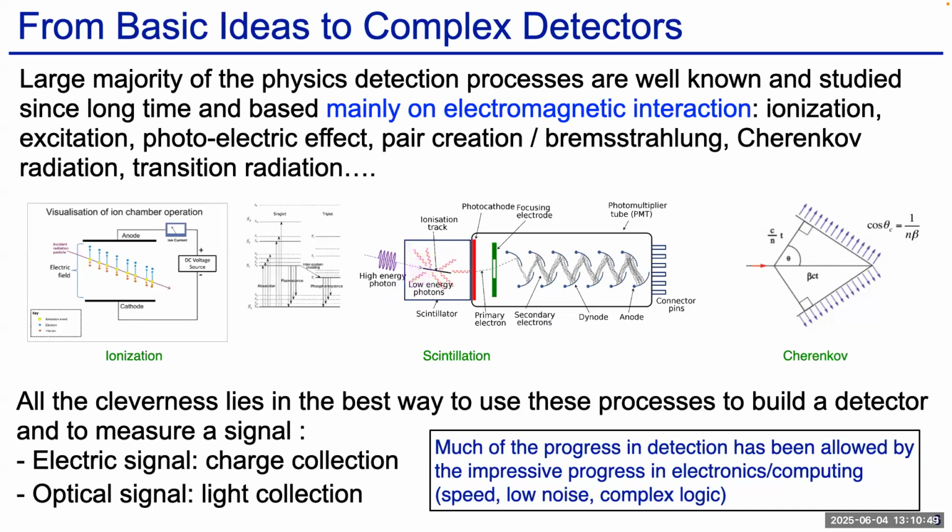Now, how do we detect photons? In the good old days, we did that with photomultipliers that have here a photocathode, then a focusing electrode, and then you have here these dynodes. They hit the first one, they create electrons. They hit the second one, and they create more and more electrons until you have a very strong signal which you read out. Those are hardly used anymore. We have silicon photomultipliers and other things, but the principle is still somehow there.